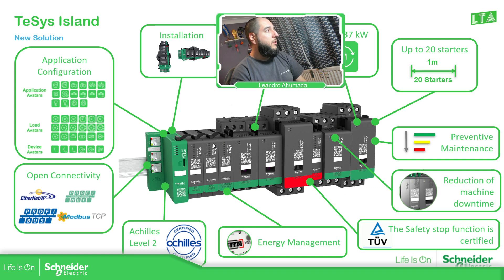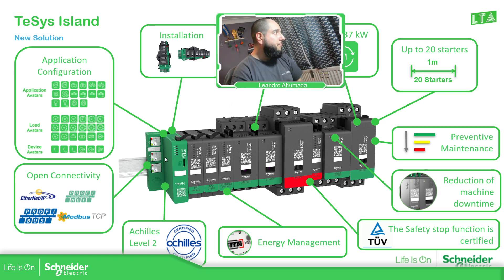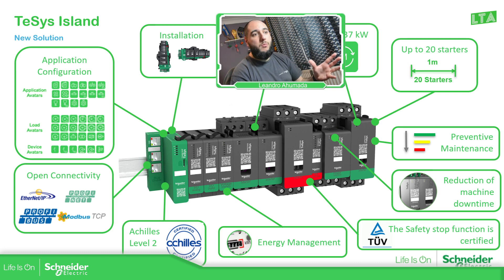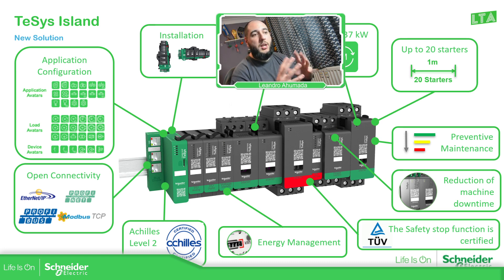These are all the features you may have with the TeSys Island. The TeSys Island has this bus coupler — the one shown here in green — and the idea is to communicate with the system. As Schneider, we can use our Schneider PLCs with Modbus TCP or EtherNet/IP. But if you want motor management, you can use any other PLC that supports Modbus TCP, EtherNet/IP, PROFINET, or PROFIBUS in order to read, write, and control the TeSys Island.